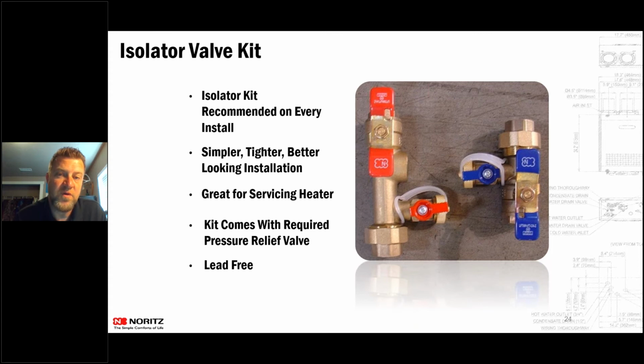If it's a recirc unit, or you're adding a recirc pump to a tankless water heater, then you do need to add an expansion tank to the system because you are introducing thermal expansion into the system. But with just straight tankless water heaters without recirc, you do not need to have an expansion tank because there is no thermal expansion within the system. As soon as you turn on that faucet, that's your thermal expansion inside the house. As soon as you turn it off, the unit turns off, and there's only about 1.5 liters of water in those heat exchangers, so you do not need an expansion tank. Having an expansion tank is still a great idea on the system, but it is not required with tankless water heaters.